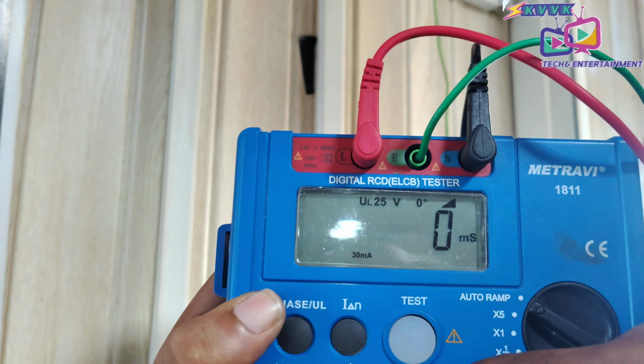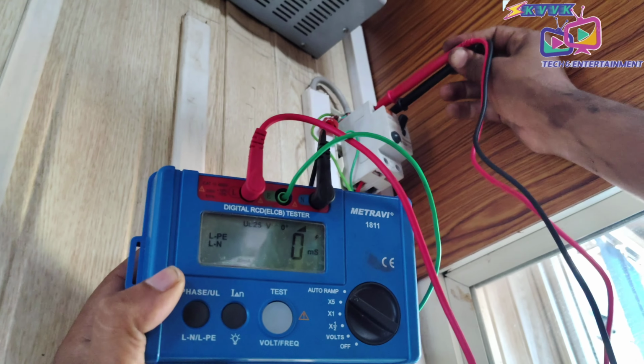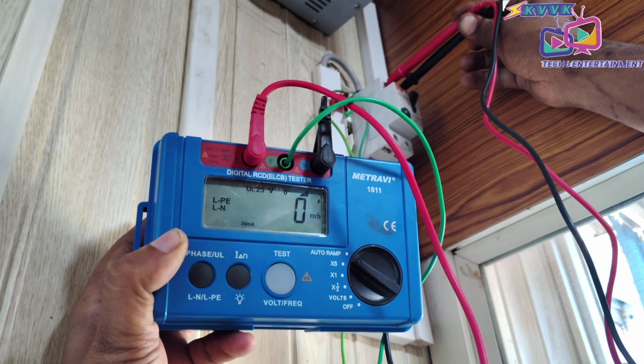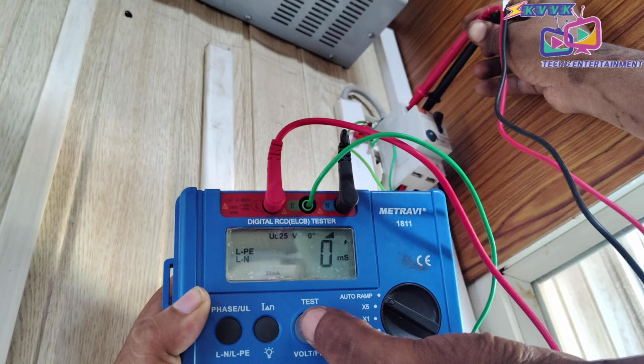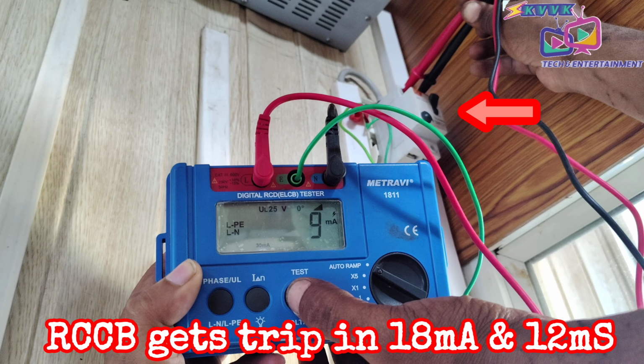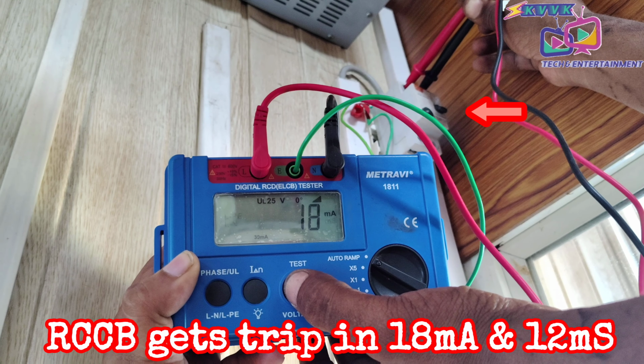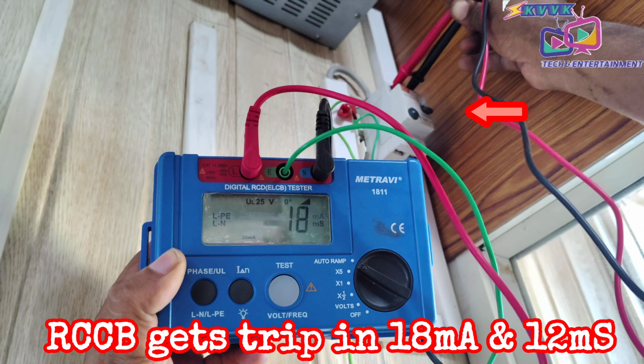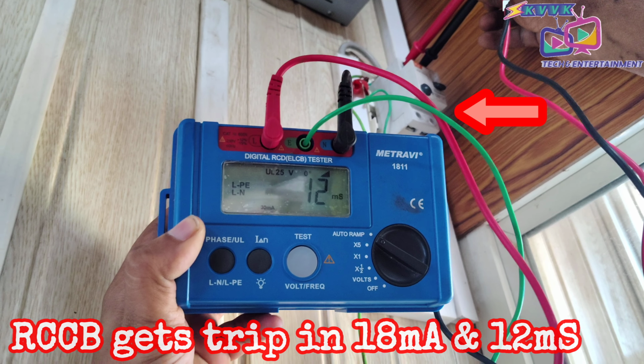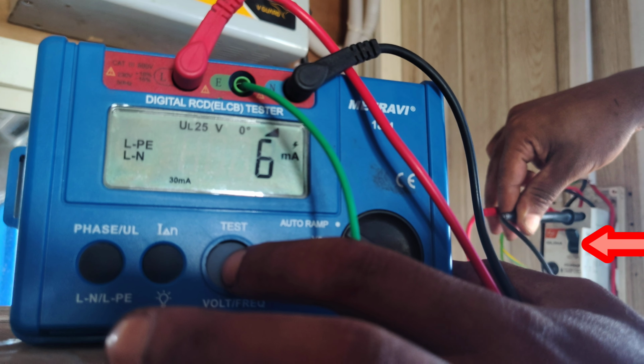Connect the terminals of the RCD to the load, phase, neutral and earth. Currently checking the correct wiring of the RCCB. After placing the connection probes, press the test button. Now you can see the applied leakage current in milliamp. Then the RCCB gets tripped at a value below the set value. I would like to show you the test again in closed view.